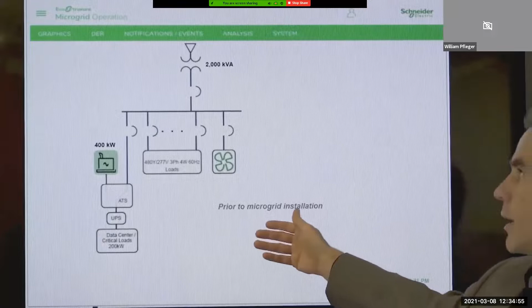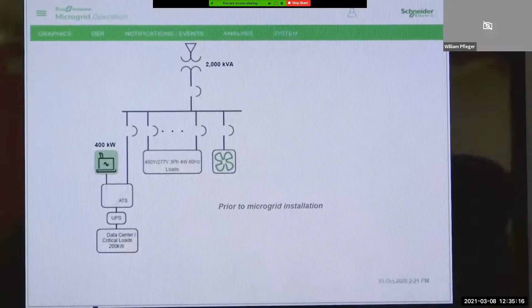And that's why we go ahead and give that HVAC load its own special symbol in our simplified one line here. And then in terms of original backup power at the site, we had a very conventional arrangement here with a 400 kilowatt natural gas generator feeding as the alternate source for an automatic transfer switch, the ATS you see here. And either utility power or generator power feeds through the ATS to an uninterruptible power supply, which then feeds the data center and critical loads in the facility.